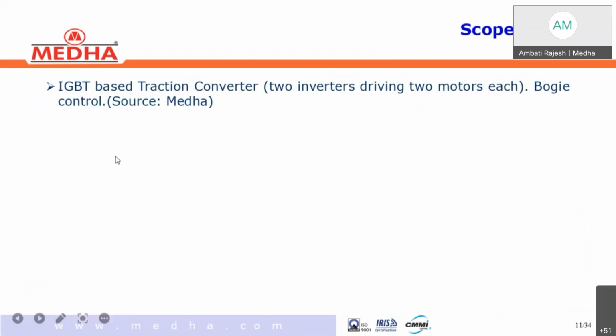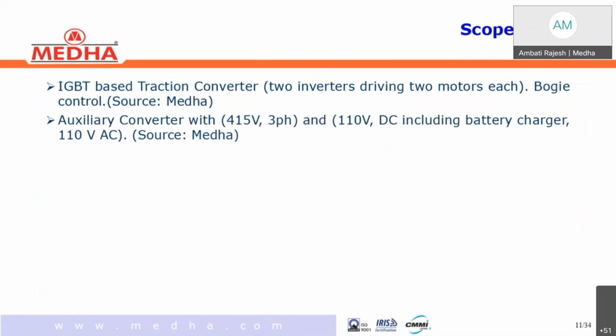As it is bogie control, each converter drives two traction motors. And this IGBT based air cooled line and traction converter is from MEDHA, 1300 kVA rating. And auxiliary converter, 120 kVA rating. It generates three low voltage signals: 415 volts 3-phase AC supply, 110 volts single phase AC supply, and 110 volts DC supply from the input, 1800 volts DC link supply. And this is also purely from MEDHA, and this is also an air cooled converter. There is a blower which works on 415 supply to cool the auxiliary converter.